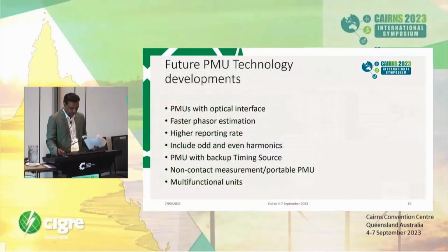Now let's see what some advancements in future PMU technology are. No matter how good a PMU is, the data accuracy will always depend on the accuracy of the instrument transformers. Hence, it is very important to have precise measurement at the source. You must all have heard about optical instrument transformers. They are actually the future of power industry measurement technology.